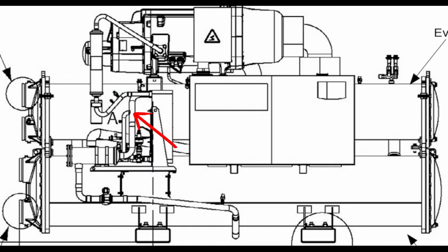And so I would assume that because we could have such extreme temperature swings with this system, maybe they put this accumulator in here in order to protect the compressor from any possible slugging, because once we come out of this tube we go straight into the screw bolts, and if we don't do something to mitigate possible floodback issues... this is not something you see on all systems that have an economizer line like this. This is one of the few I've seen that actually have an accumulator implemented. And then again, that is my assumption. This is an accumulator. If the manual is worth anything, it might explain that to me.